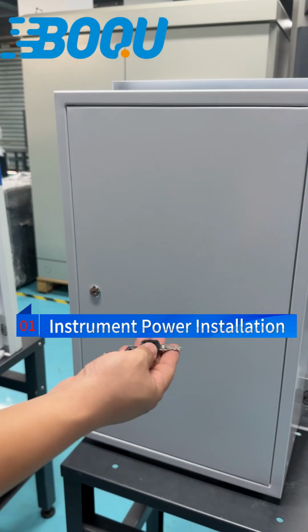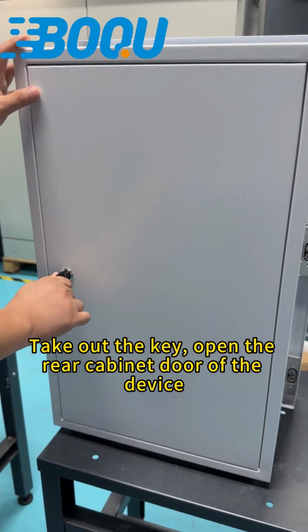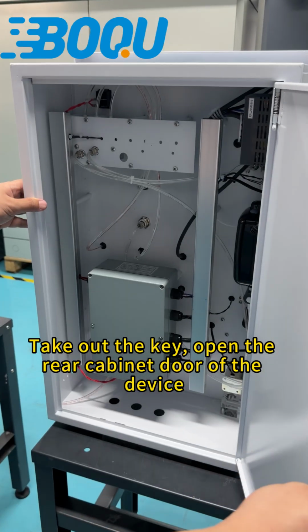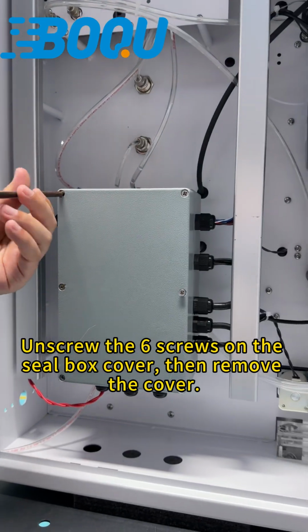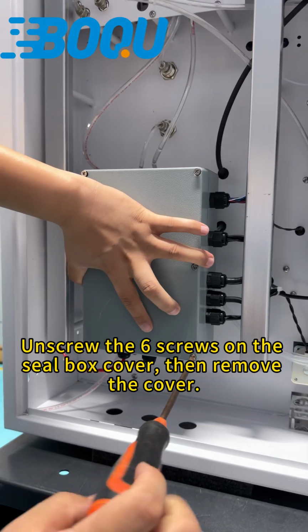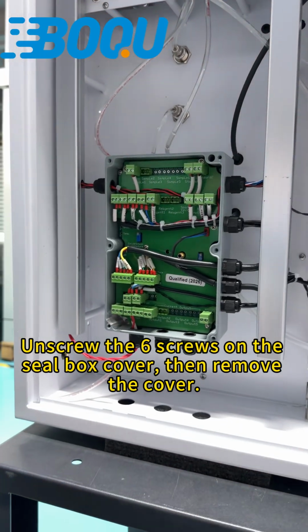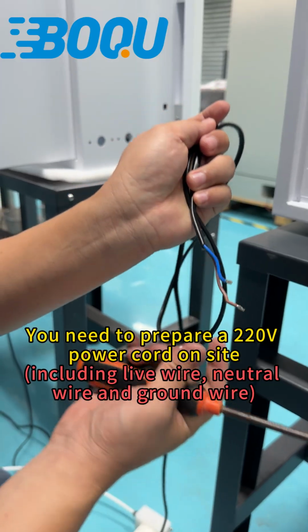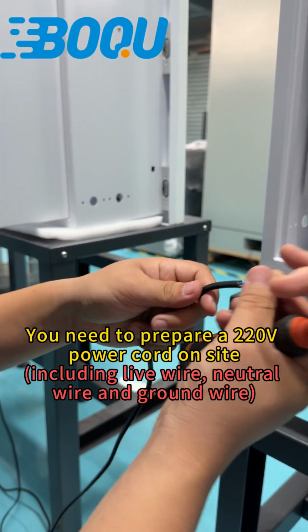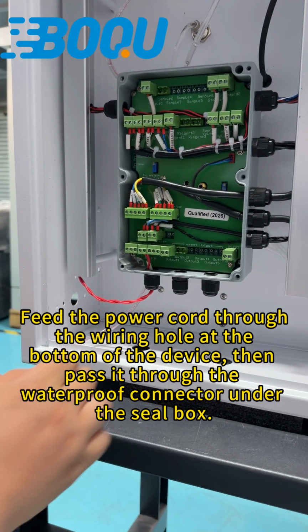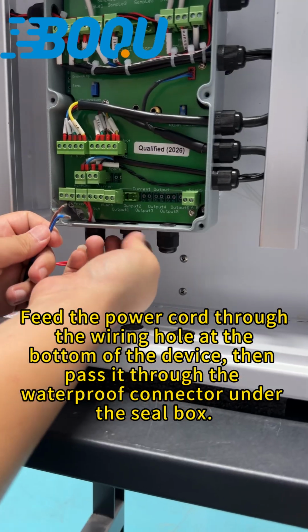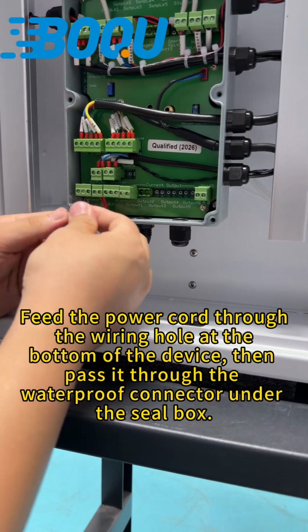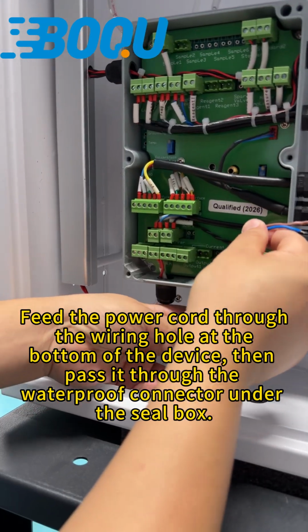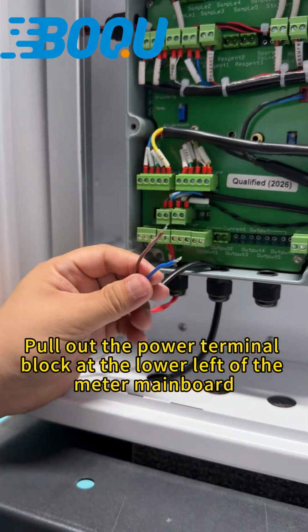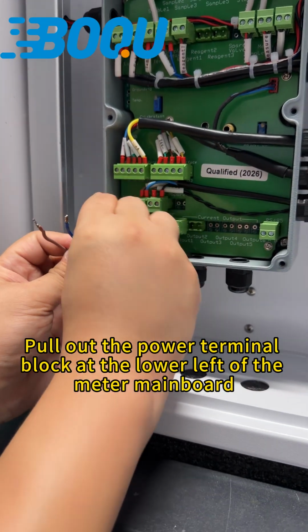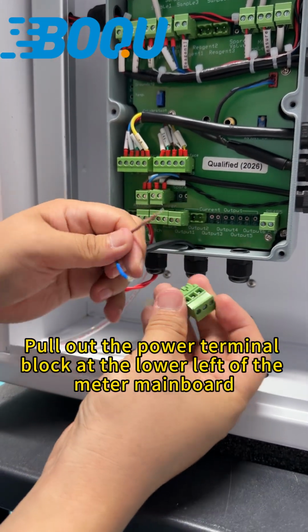Instrument power installation. Take out the key, open the rail cabinet door of the device, unscrew the 6 screws on the seal box cover, then remove the cover. You need to prepare a 220 volts power cord on site. Feed the power cord through the wiring hole at the bottom of the device, then pass it through the waterproof connector under the seal box. Pull out the power terminal block at the lower left of the meter mainboard.